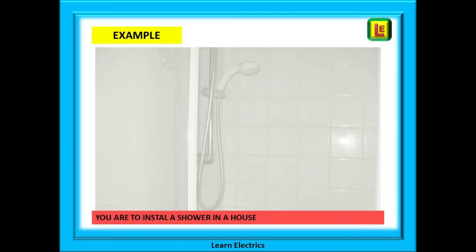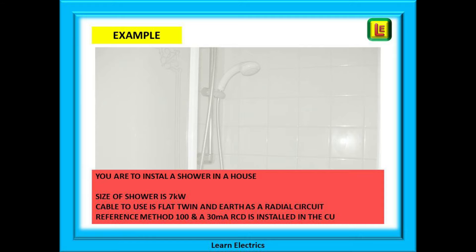Let us now work through an example in steps as you would do in practice. We have been asked to install a shower in a house. We know the size of shower is 7 kilowatts or 7000 watts. The cable is flat twin and earth, being installed as a radial circuit, and we will be laying cable above the ceiling where it will be in contact with 100 millimetres of loft insulation. There is also a 30 milliamp RCD already installed in the consumer unit.